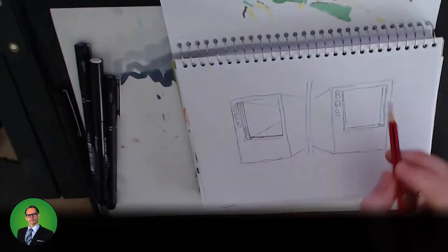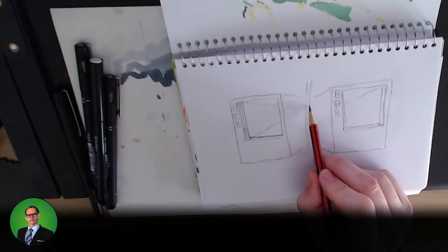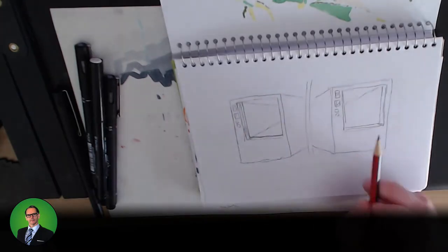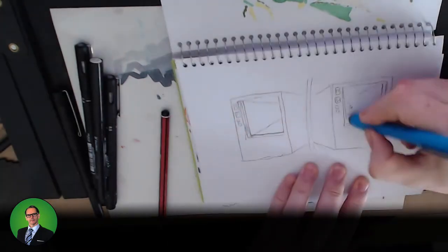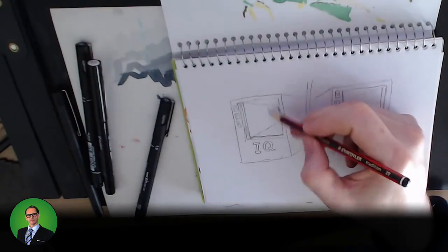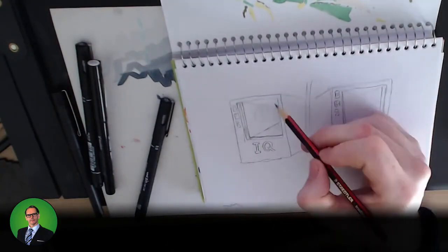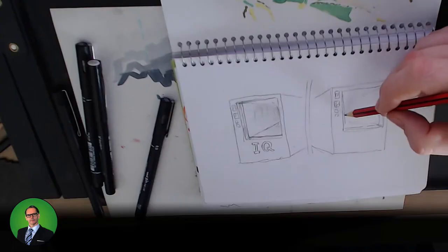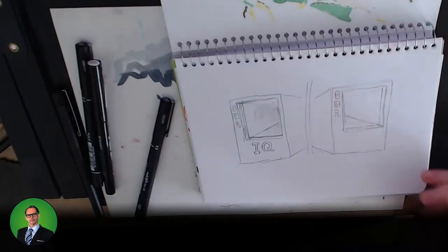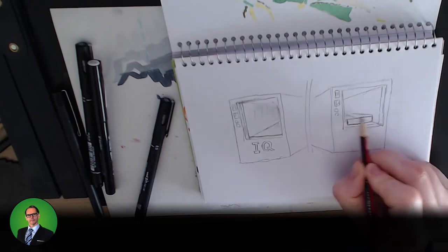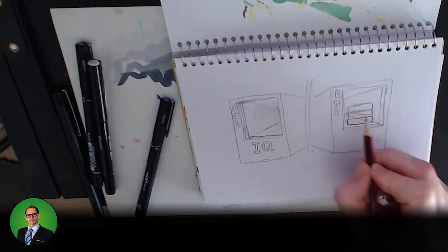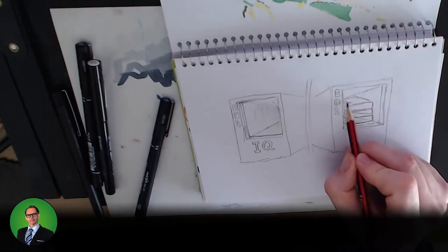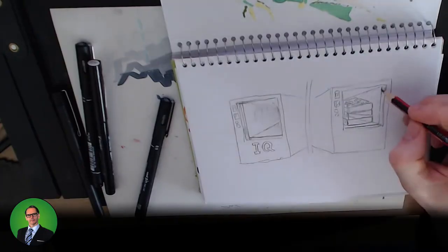So here we go. A couple of really badly drawn autoclaves with regards to perspective, especially when it comes to the inside of them. But the main goal here is to show an empty autoclave, which is actually supposed to be operational qualification and not installation qualification, alongside a loaded autoclave, which would form part of your performance qualification.